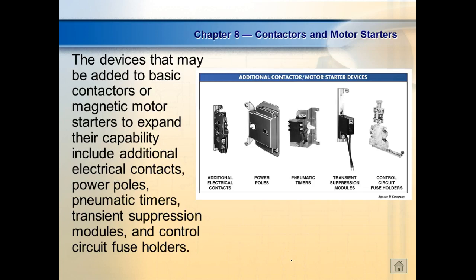And of course, we know that they can strap all types of things on these contactors. They can add additional contacts. We call them auxiliary contacts. Some of them actually have additional power contacts on them, right? We could add timers on there. We'll get into later on where we can actually put timers on some of these contacts. We have what we call off-delay timers and on-delay timers. We'll look at that. Transient or surge suppression, we might add those to help extinguish the arc on our contact, and then we might even have fuse holders on the contacts themselves. But most of these contactors allow you to add different elements. All we've seen so far is these guys up here. The relay that we have has an additional power pole on it.